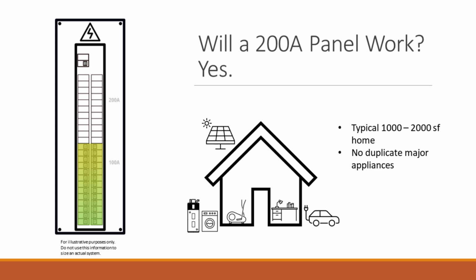In addition, the PV system has been sized to meet the minimum T24 requirements. The load is probably going to be somewhere around 120 to 150 amps, which fits pretty comfortably within our 200 amp panel. So I feel pretty confident saying that with this typical home, yeah, our 200 amp panel is going to be just fine.